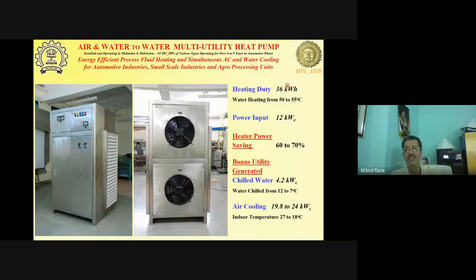So in this particular example, heating duty was 36 kilowatt, that is 50 to 55 degree heating. Power input was only 12 kilowatts. So the heating COP was 3, and so about 66% energy saving on the heating bill here. And then the bonus utility produces chilled water as and when required, and air conditioning. So whenever air conditioning would be 24, plus 12 will give you 36 of heating. Or if you're tapping part of the cooling effect in the chilled water, then the air conditioning will appropriately reduce. And air temperature from the room air at 27 would be cooled down to about 18. So it would be cooled, dehumidified air.